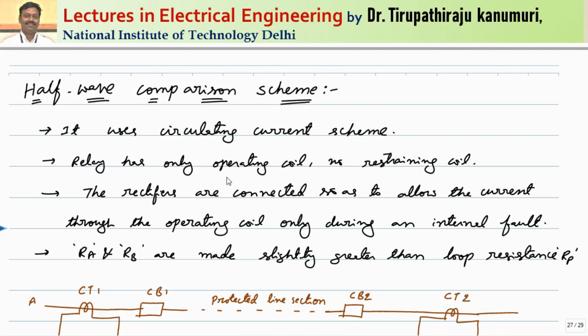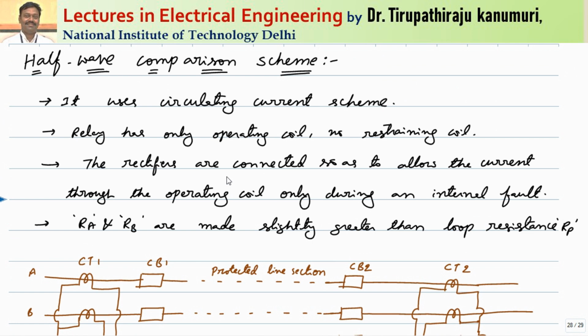The next method is the half wave comparison method. This uses the circulating current scheme. We have already discussed the circulating current scheme in our module number 3. We have seen that the disadvantage of the circulating current scheme is that the current will continuously circulate in your pilot wires.